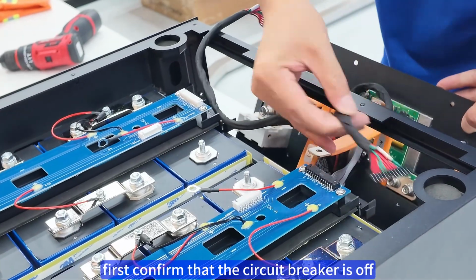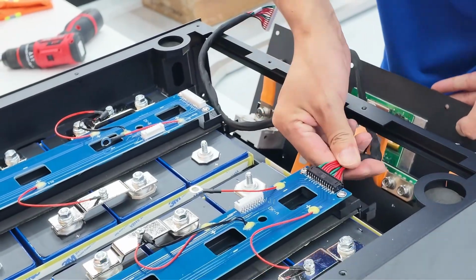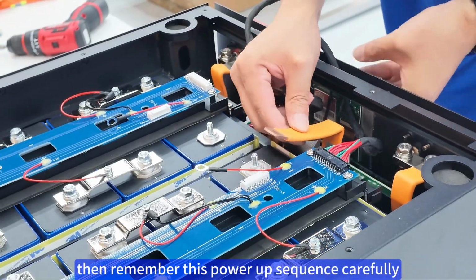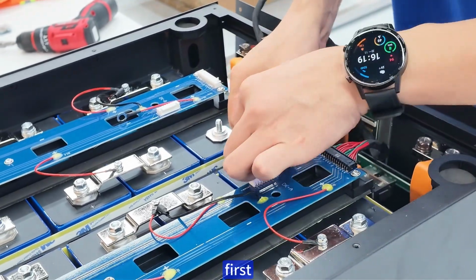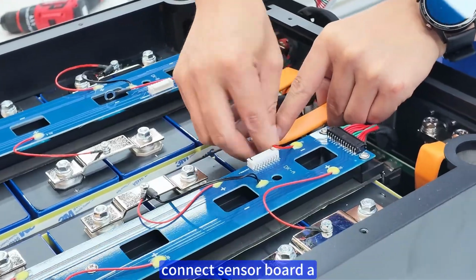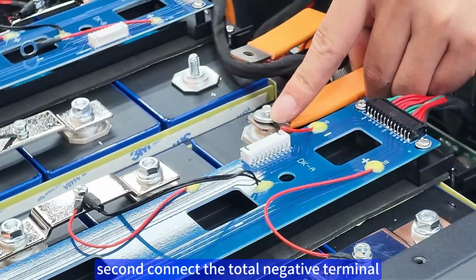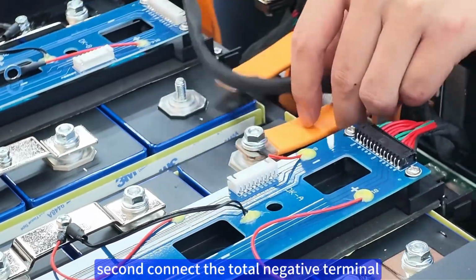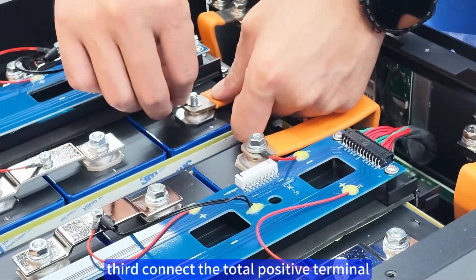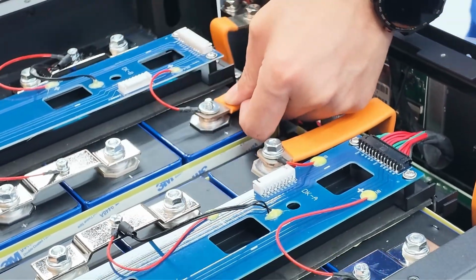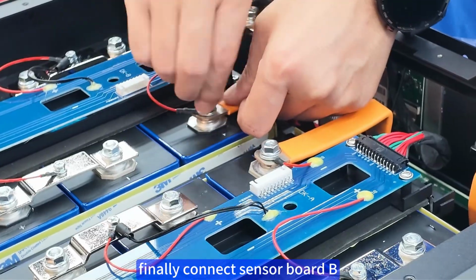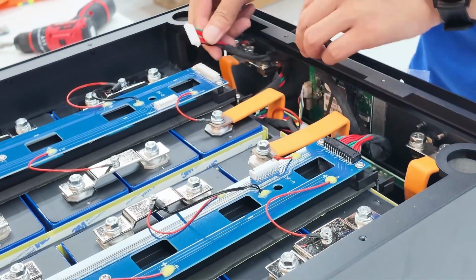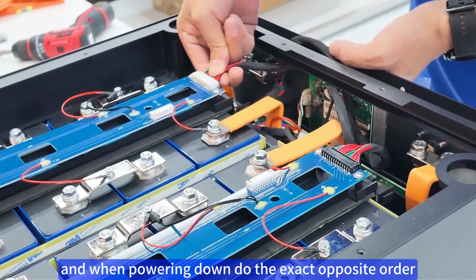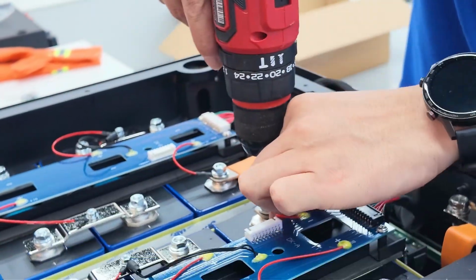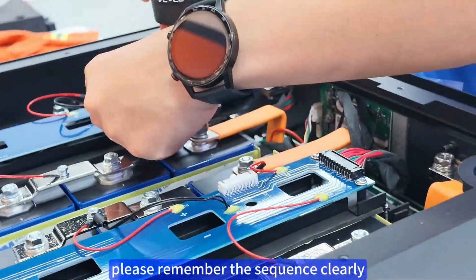First, confirm that the circuit breaker is off. Then remember this power-up sequence carefully: first, connect sensor board A; second, connect the total negative terminal; third, connect the total positive terminal; finally, connect sensor board B. And when powering down, do the exact opposite order. Please remember the sequence clearly.